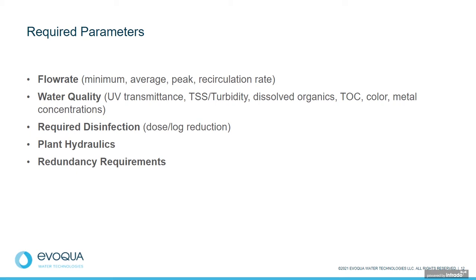Water quality, UV transmittance is extremely important. It is the amount of UV light that penetrates the water, and there are things that absorb UV from turbidity to dissolved organics and TOC. Color is a big absorber of UV. Are there metal concentrations? These are the things that we're going to ask about your water quality.